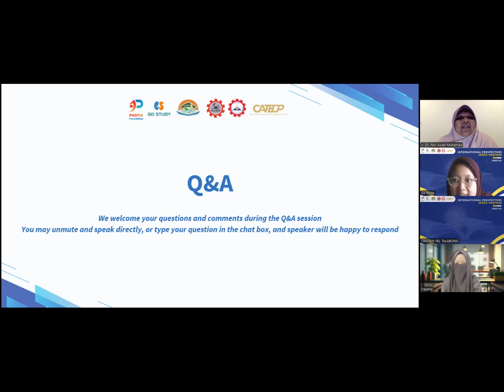Even for partial discharge, the equipment is in operation when we have partial discharge. There are conditions where there is partial discharge. So there are technologies which do not interrupt the system. You have the partial discharge UHF sensor, a very high frequency partial discharge sensor. So there is the telecommunication and sensor part. The technology updates really help with the equipment used daily; we try to make it more convenient.